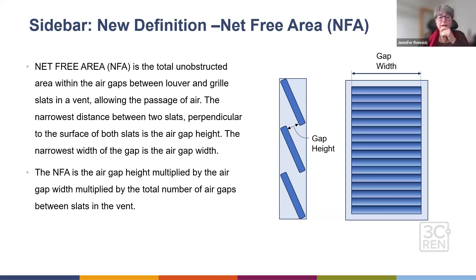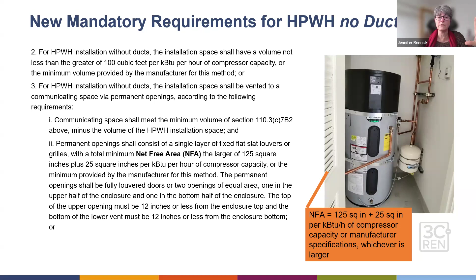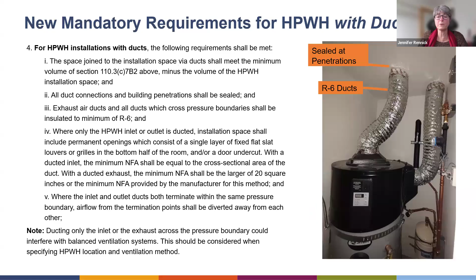Also, another thing they're really pushing with these mandatory requirements is to understand that if you're ducting to and from another space, you need to make sure that other space meets the volume requirements. And the cross section of the ducts, grates, or grills all have to be large enough. The main reason they put all this in the code now is because these appliances, to function properly and get the high COP, need a certain volume of air, and they don't work so well if you restrict their air volume too much.